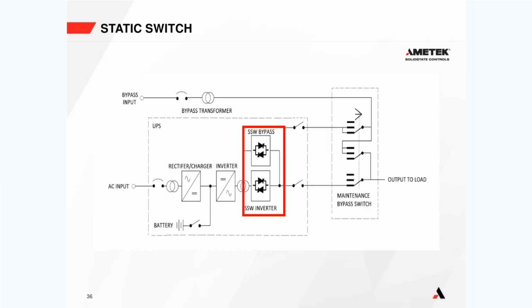Another place we use SCRs or thyristors in a UPS system is on the static switch. A static switch is quite simple. Static as in no moving parts, and switch as it is a switch. So it's a switch with no moving parts, an electronic switch. That is what a static switch is.